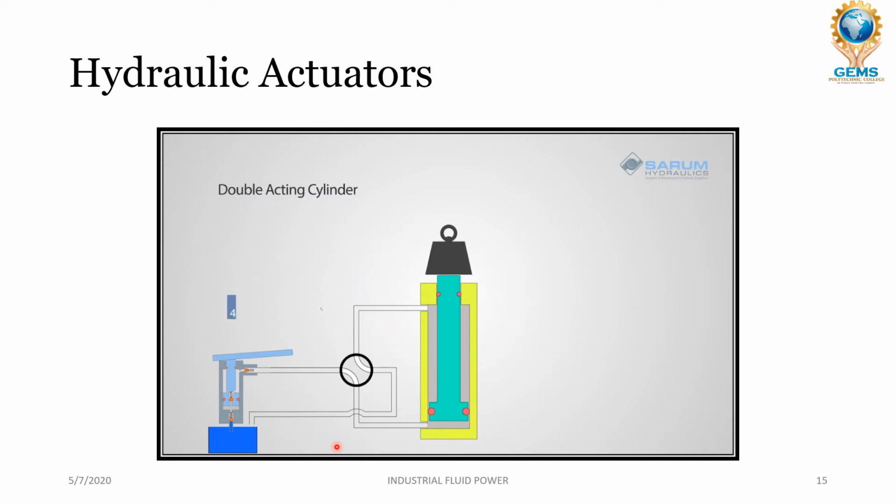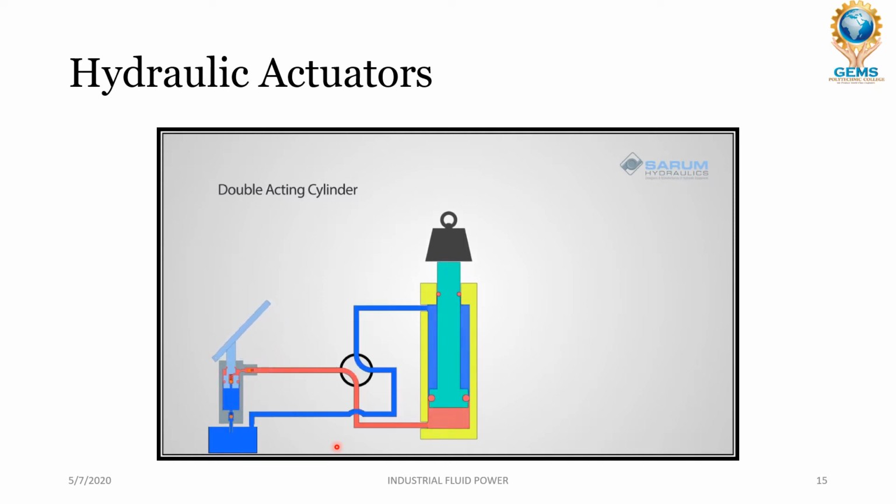You'll need a four-way directional control valve to operate your double-acting cylinder. We've added one to our micropack hand pump. There are two connections on this valve, one at either end of the cylinder. Pressurize the bottom of the ram or full bore end to generate force. You need to connect the upper chamber or reduced bore to the tank, or the ram will jam.